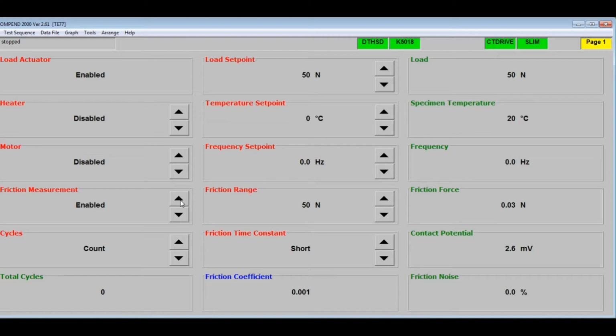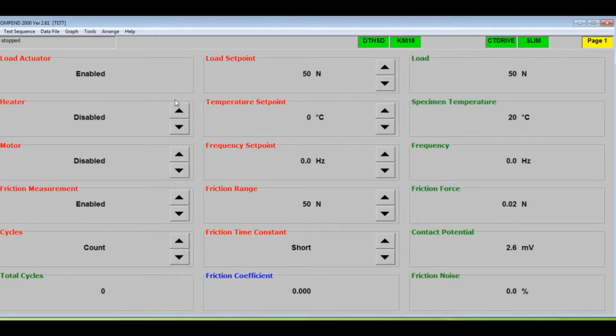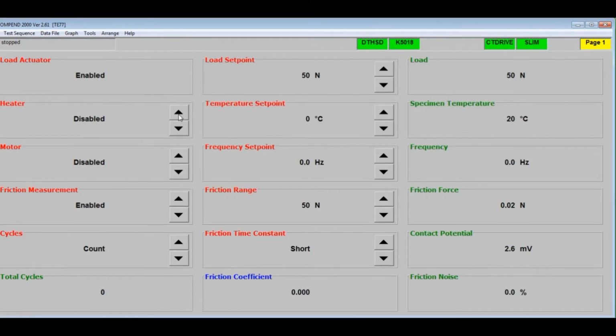The friction noise reading is an analog measurement of the orderliness or smoothness of the instantaneous friction signal. Please refer to the manual for further information about friction force measurement and signal processing. The value in the blue friction coefficient box is that derived from dividing the time smoothed friction force signal by the measured load.